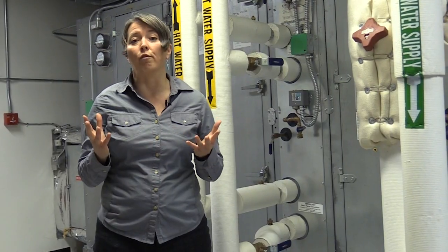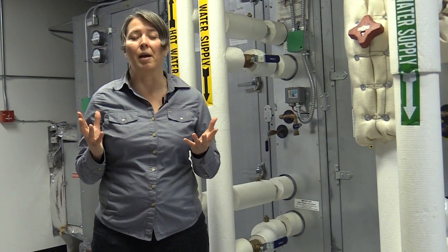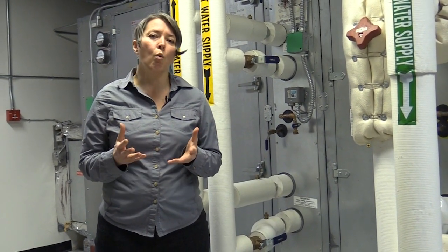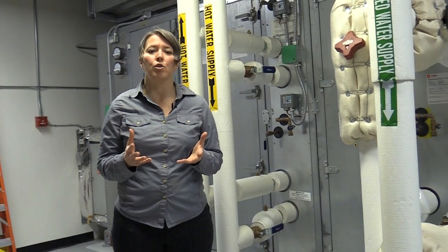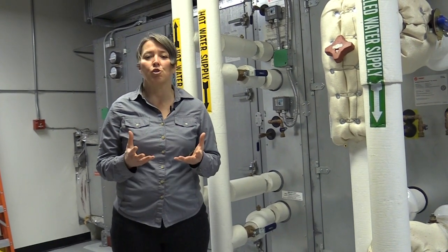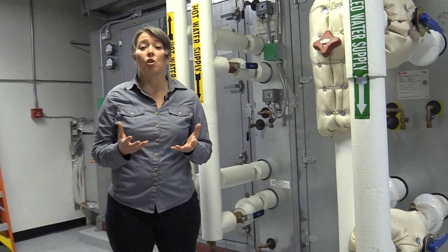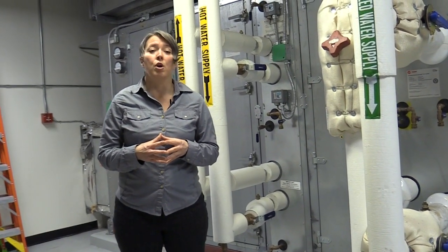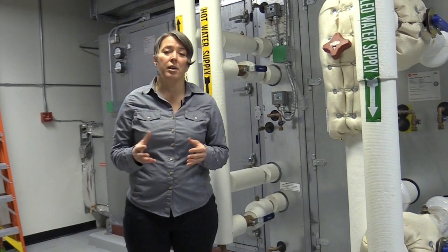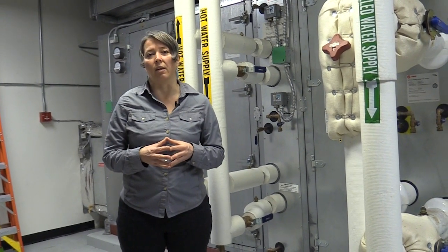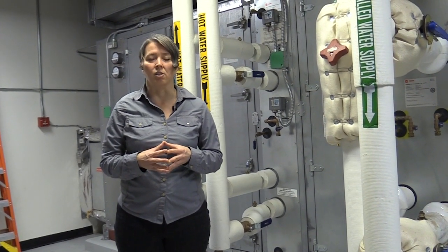Manufacturers sometimes will ship these units with one or the other type with no regard for where it's going to be installed and what climate. So it's good to know what type of control you have, what type of sensor you have, because this could also be an opportunity to retrofit that sensor depending on your climate and application and the control strategy. You might see additional savings.